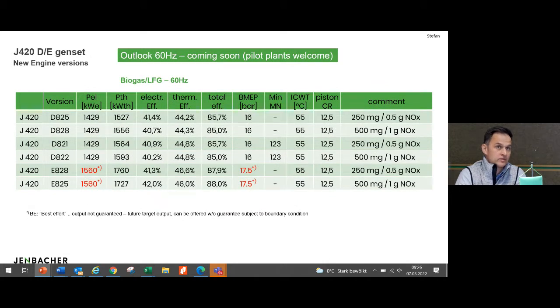Biogas and landfill gas versions are as well available. And here, as said, on the biogas side, the same. If the gas TA is fulfilled, we can have as well there our new steel piston versions available with the 17.5 bar BMEP, so or the 1560 kW on 250 milligram NOx or 0.5 grams and 1 gram NOx for as a future target for an improvement of the 60 Hz versions.